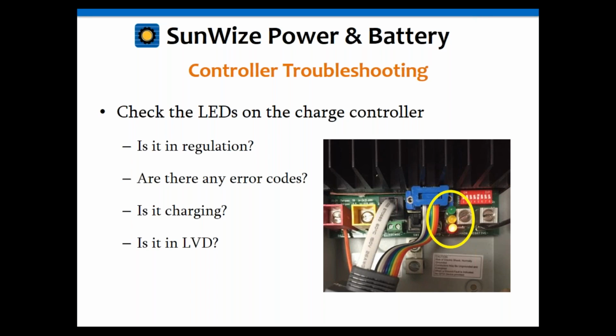And it can tell you whether the charge controller is in regulation. There might be error codes. It might tell you whether it's an LVD or whether it's charging or not. And the error codes might tell you what's going on. It might tell you there's a short on the load. They might tell you there is a problem with the array. It might tell you that there's some other fatal error. It might tell you of a high temp alarm. So looking at those LEDs, and having the manual for the charge controller so that you can look up those error codes while you're there and figure out what they mean, can be very handy as well.